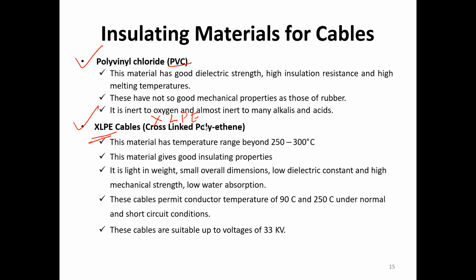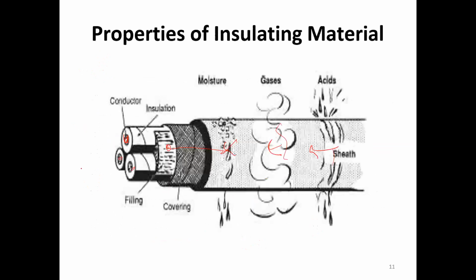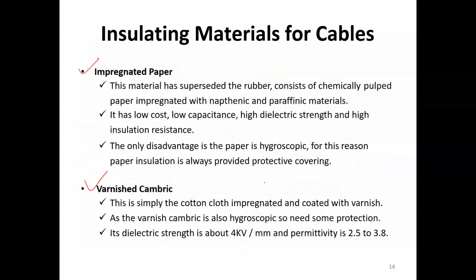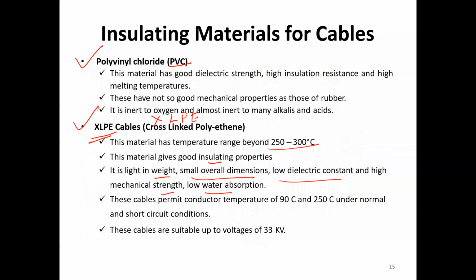This material is generally used for insulation of cable because it has a temperature range beyond 250 to 300 degree Celsius. The material has good insulating property, lightweight, small overall dimension, low dielectric constant, high mechanical strength, and low water absorption property. All the properties we listed earlier are available in this material. These cables permit conductor temperature about 90 to 250 degrees under normal and short circuit conditions.